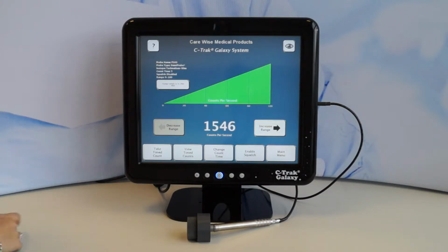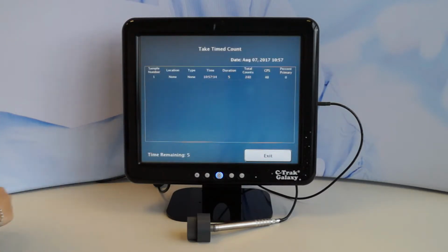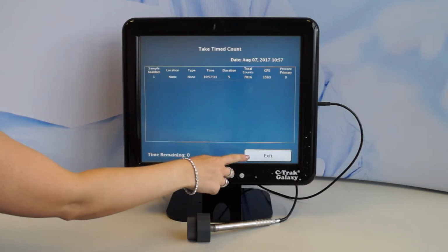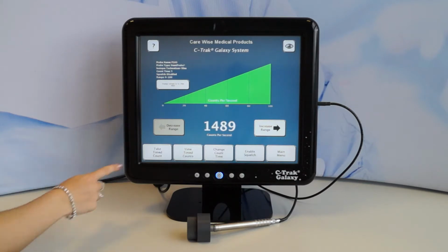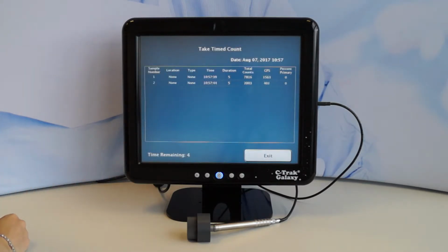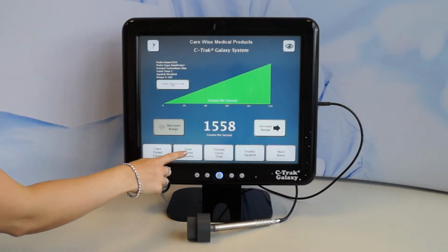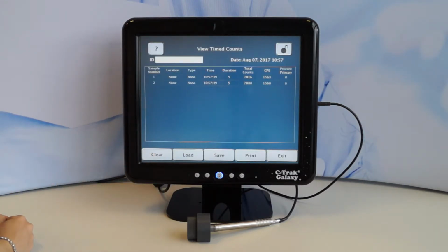Many surgeons like to take time counts of the injection site, background and specimens. To do this, use the bottom left-hand button and press Take Timed Count. This will take a total number of counts within a 5-second window. After this, you can either press the Exit button or the system will reset to the count screen after a few seconds. To go back and view the timed count, press the View Timed Counts button and you will see all timed counts taken during a procedure.